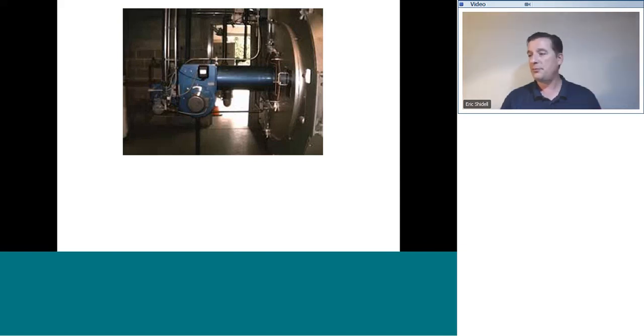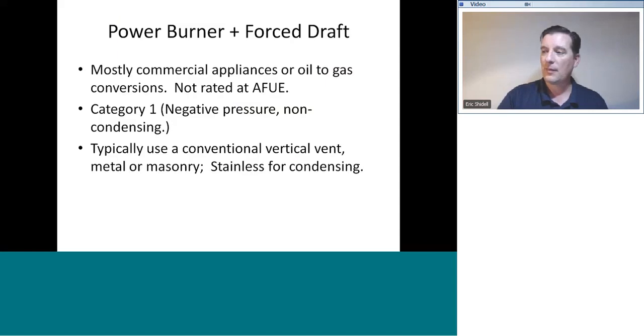Power burners and forced draft are mostly commercial applications or oil to gas conversions. They're so big they're not rated in AFUE, just like a big commercial truck isn't rated in EPA miles per gallon. They're normally going to be category one, which is negative pressure and non-condensing. Once again, negative pressure vent. They typically use a conventional vertical vent, which may be steel, may be masonry. If it's going to be condensing, some of these are condensing appliances, it'll be stainless steel. Condensing appliances are pretty rare, though, in that category, but they do exist.